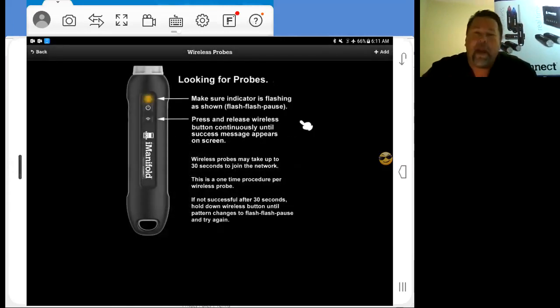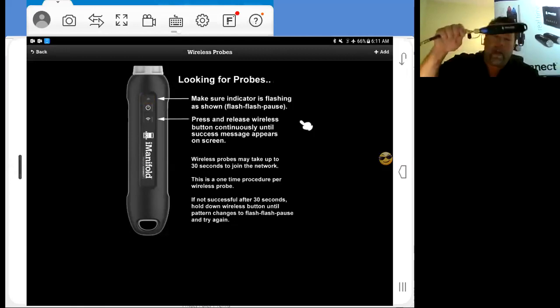Now, if you have an iManifold, you can keep going. We can pair up to 12 probes on the system. If you have an iManifold that you're using for multiple circuits, you're going to have these highs and lows as well. I'm using iConnect today. On my low pressure probe, I installed my service tee in here. That way I can add refrigerant, I can subtract refrigerant. This is before, of course, the flexible hose here.